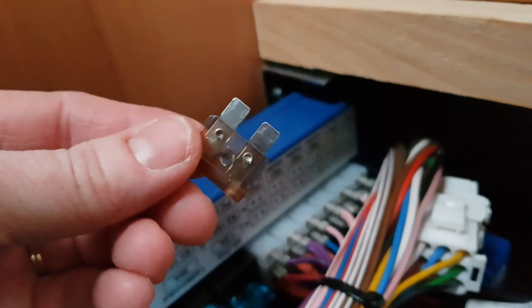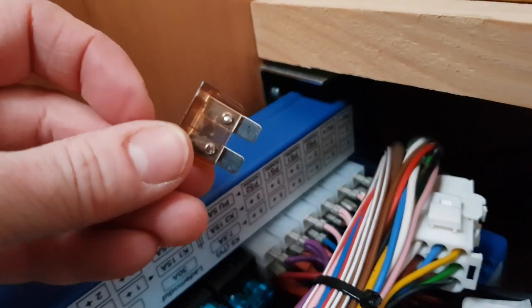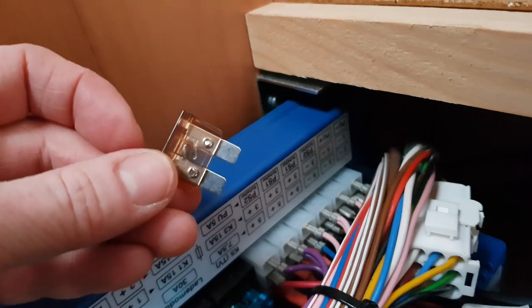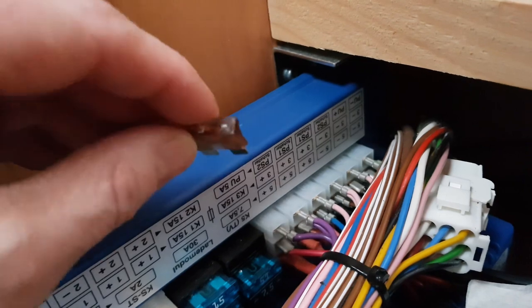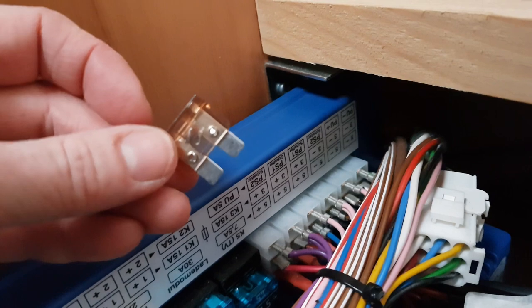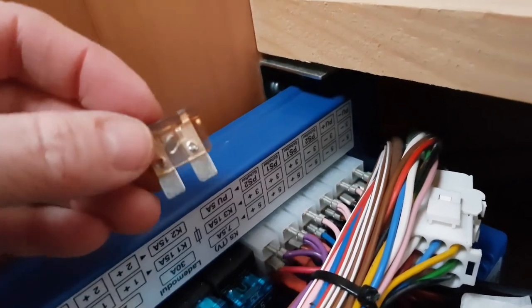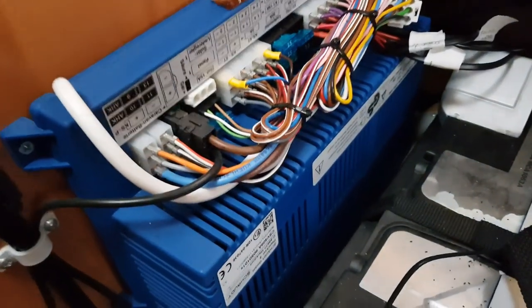The pump is not running. Hopefully it looks okay — it's just a simple pump and the tank is completely dry apart from a spot of condensation. It doesn't look like it's exploded or anything. The only other thing to check is the fuse — I think it's this brown one on the top, number five. And yes — there looks like there's a bit of a burn mark in the middle. Maybe the pump was frozen inside and yesterday when I was fiddling with the taps I clicked it on and it tried to run and drew too much current. Maybe the fuse has saved me as well as the flexible pipes.